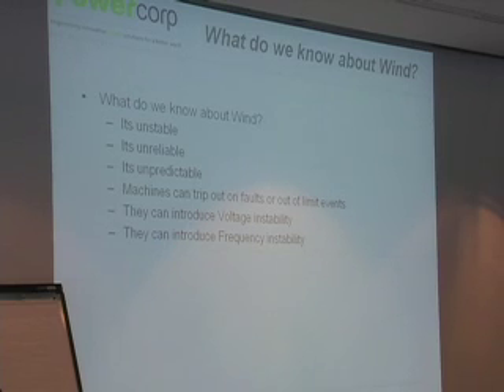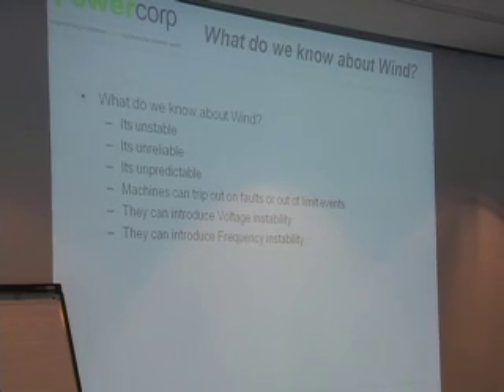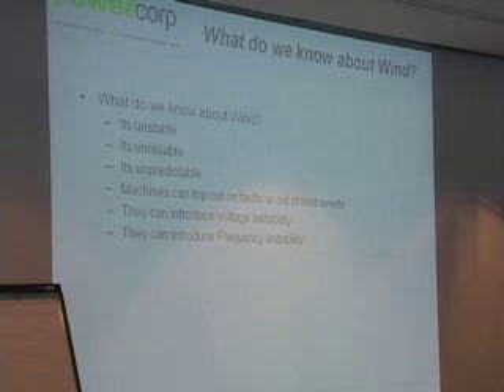They introduce all sorts of fun things on the grid. They have the great capability of just turning themselves off to protect themselves, like a diesel engine - you don't get any warning, of course. They have characteristics or parameters that say we will work inside these frequency and voltage limits, and they're generally the ones causing the problems to frequency and voltage. If they go outside those limits, they're out of here - fix that problem and we'll come back later. Which is all well and good on a large grid like Anchorage or the lower 48, but on a small wind diesel grid, it's quite an interesting ride.